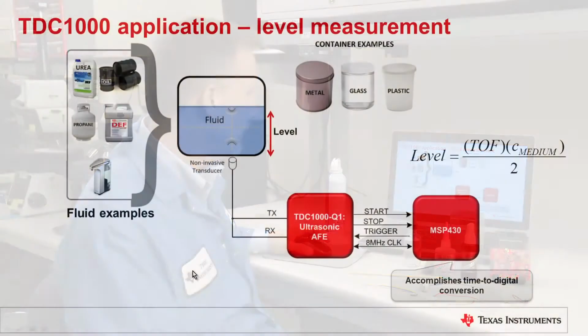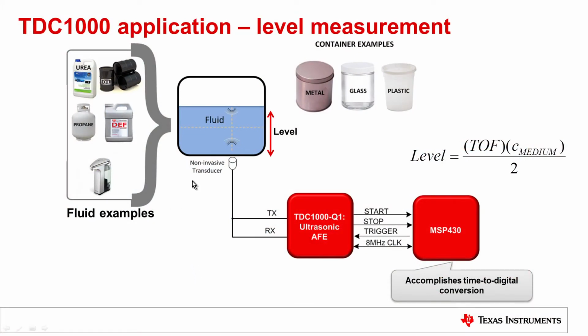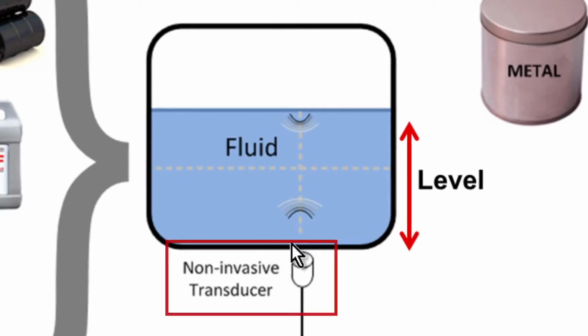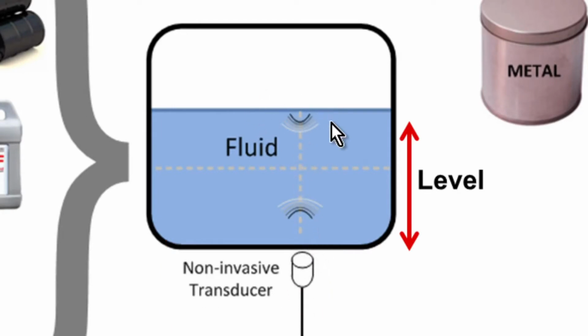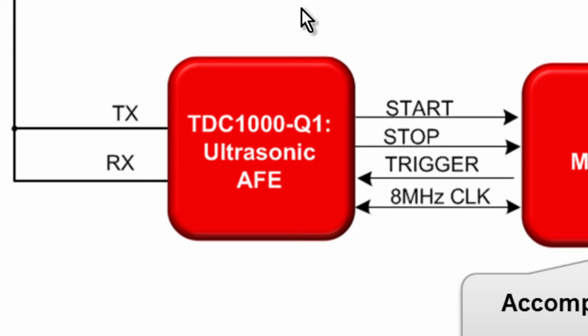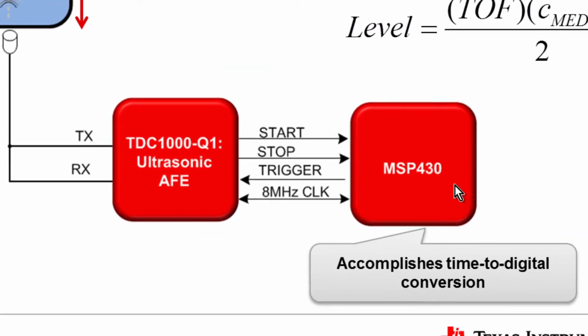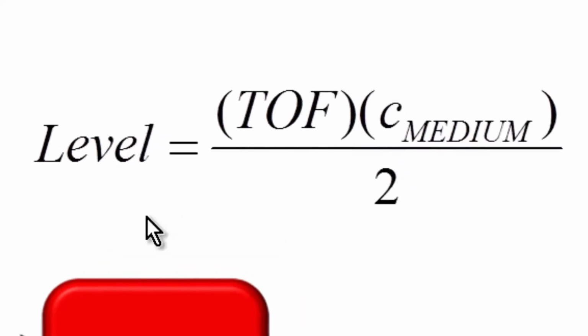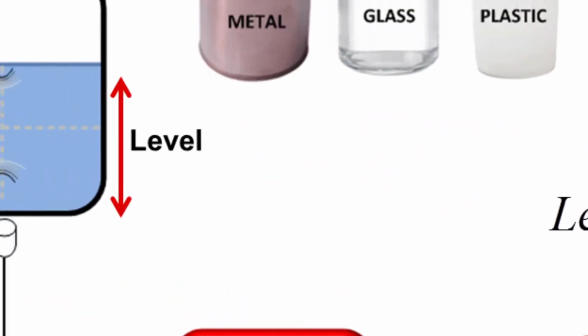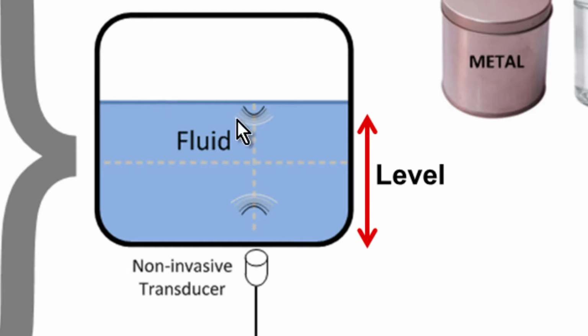Let's talk a little bit about the applications for this. A pulse echo application is best illustrated for level. In this case, I've got a non-invasive transducer mounted outside my container that's inducing energy into my medium, and at that medium-air interface, I'm getting a returning echo. The TDC-1000, connected to an MSP430 or some other microprocessor, can then convert that into a time of flight calculation. With that time of flight information and the speed of sound of my medium, I can then determine the level or the height of that fluid in that container.